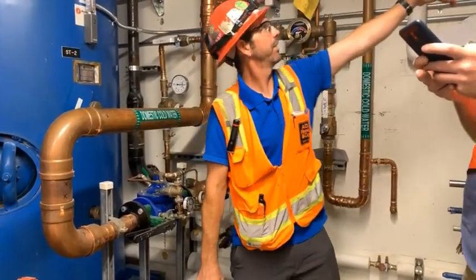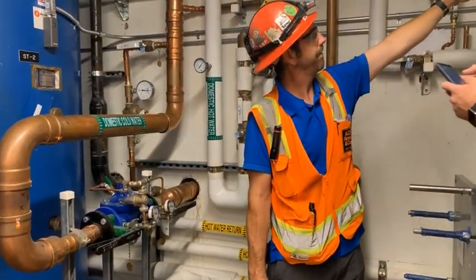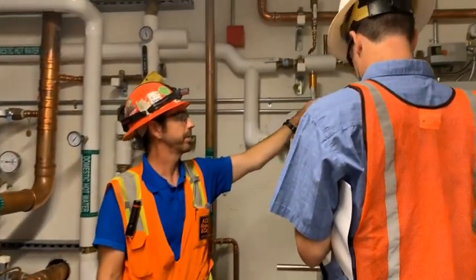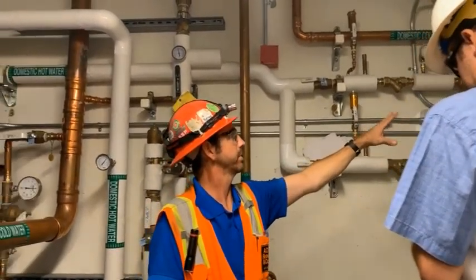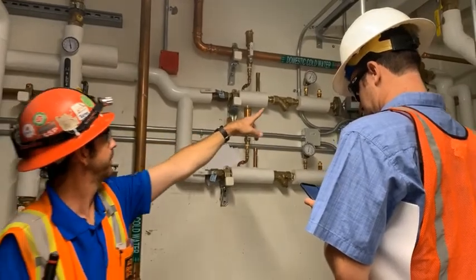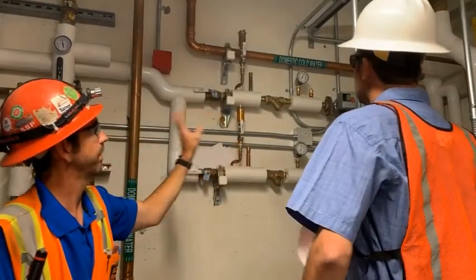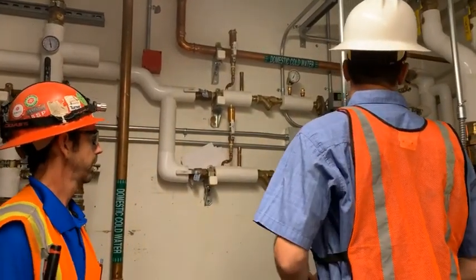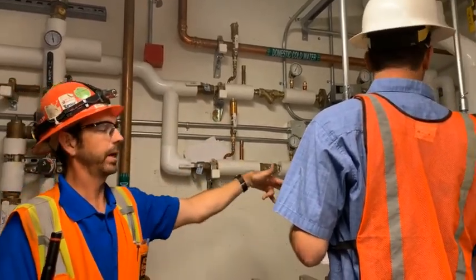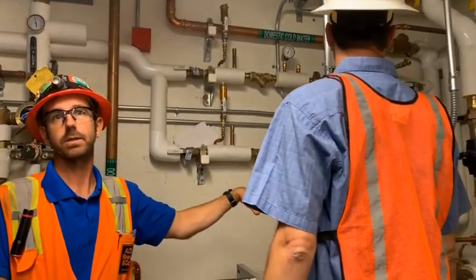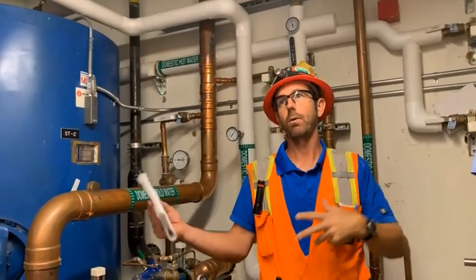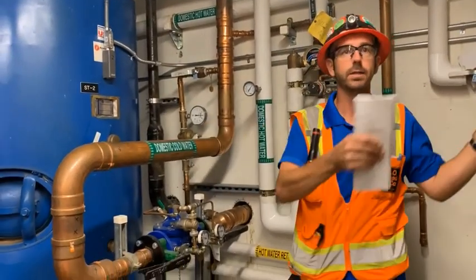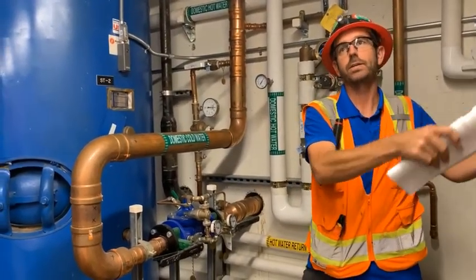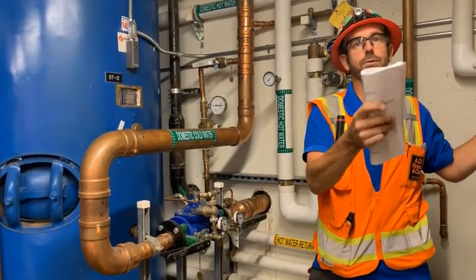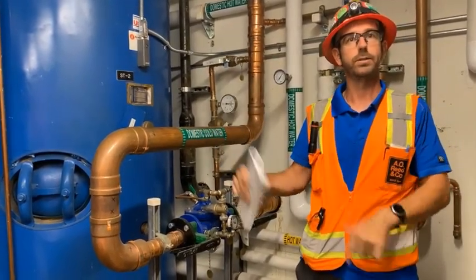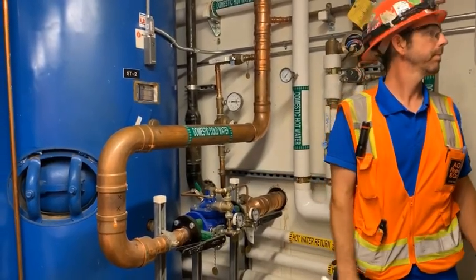There is a check valve on the cold water inlet after we turn into the heating hot water, or the domestic hot water system. So that's the main check valve up there to isolate the hot system from the cold system. Again, the cold water makes up into the inlet of the heat exchangers, okay? That's the makeup for the hot water system. It's not making it into the tank, it's making before the heat exchanger. So if there is a demand, we could already start preheating that water through the heat exchanger and not start cooling the tanks down, okay?